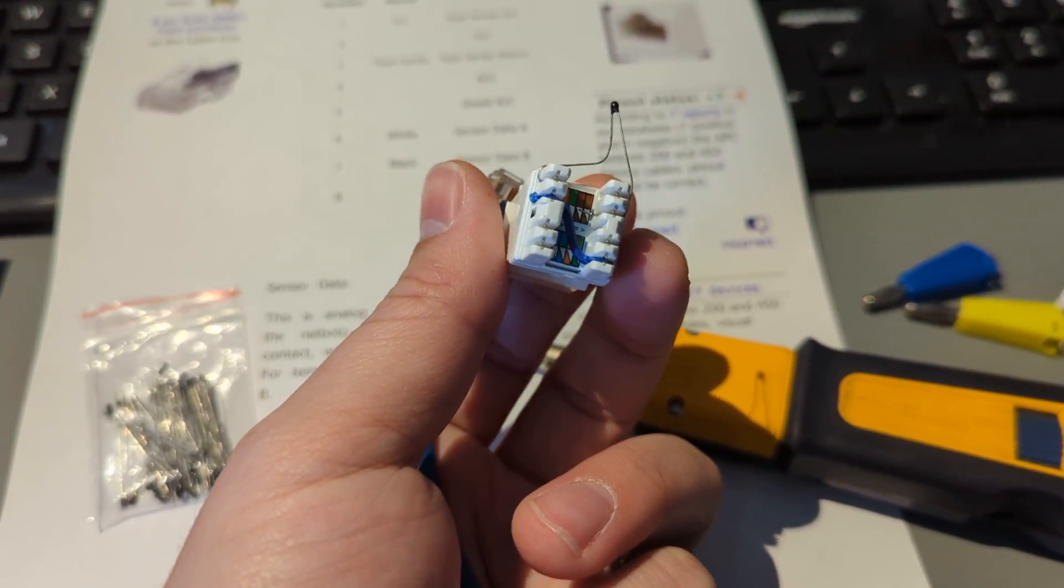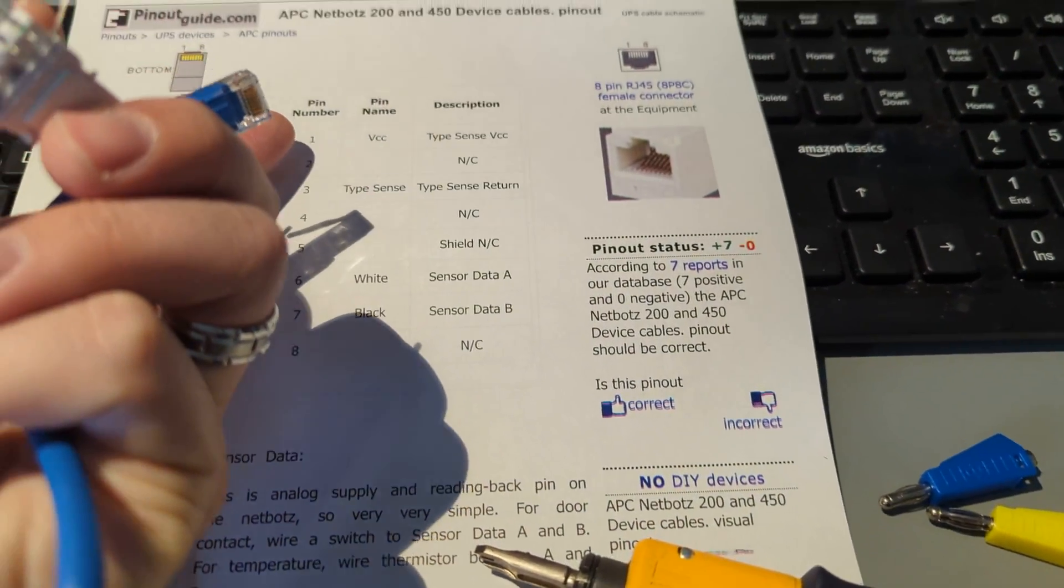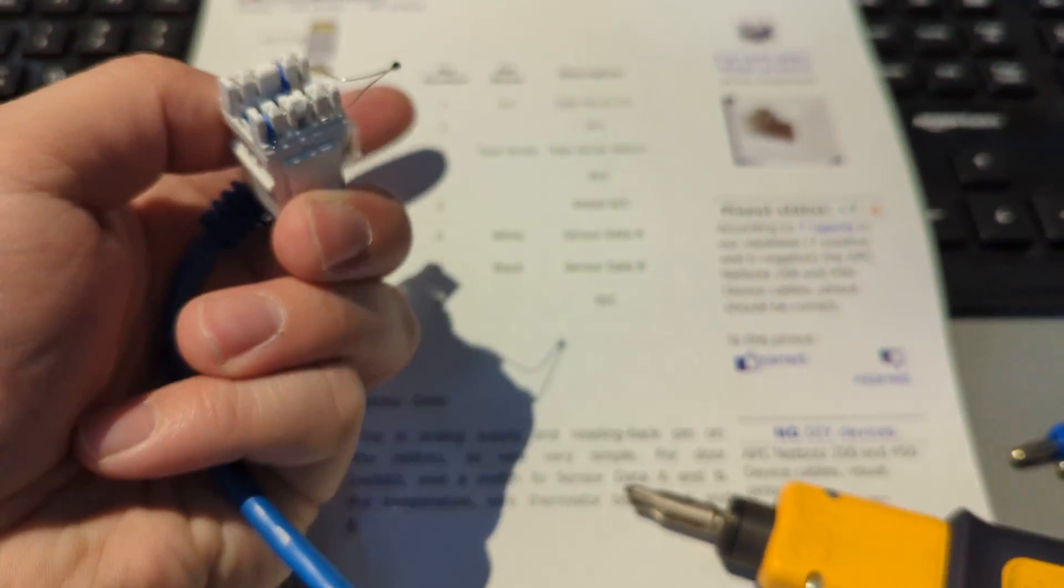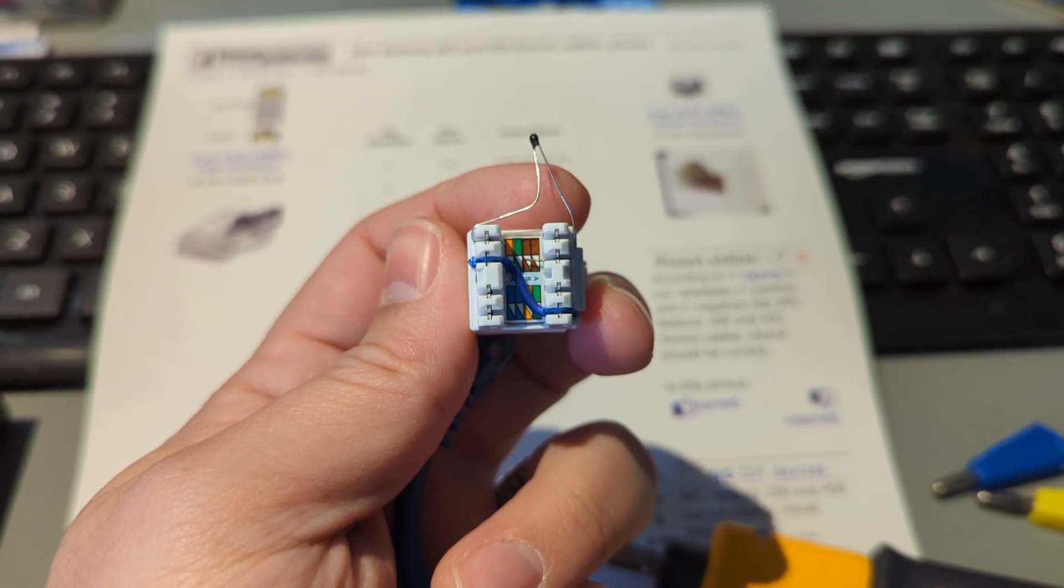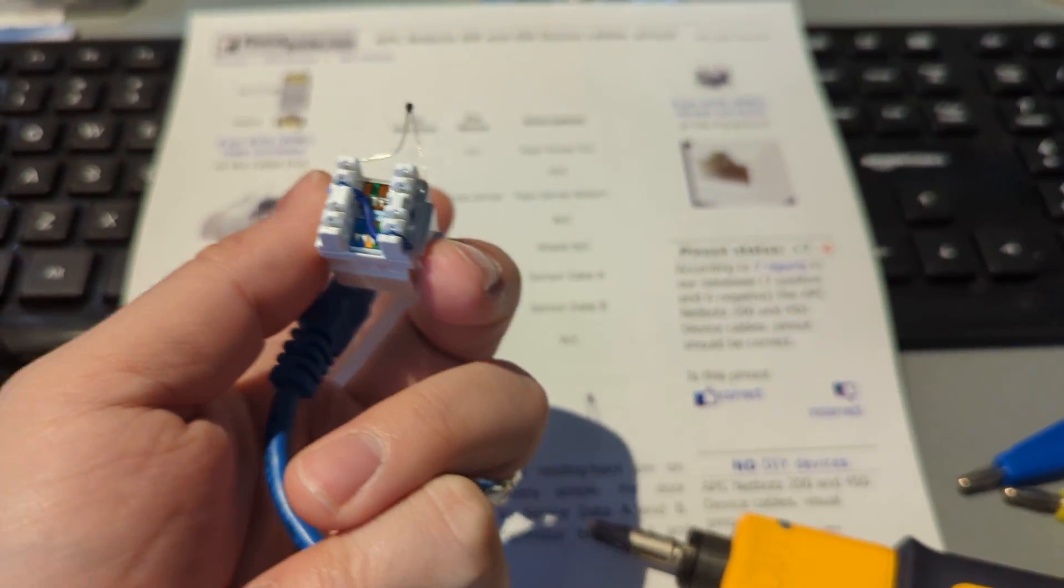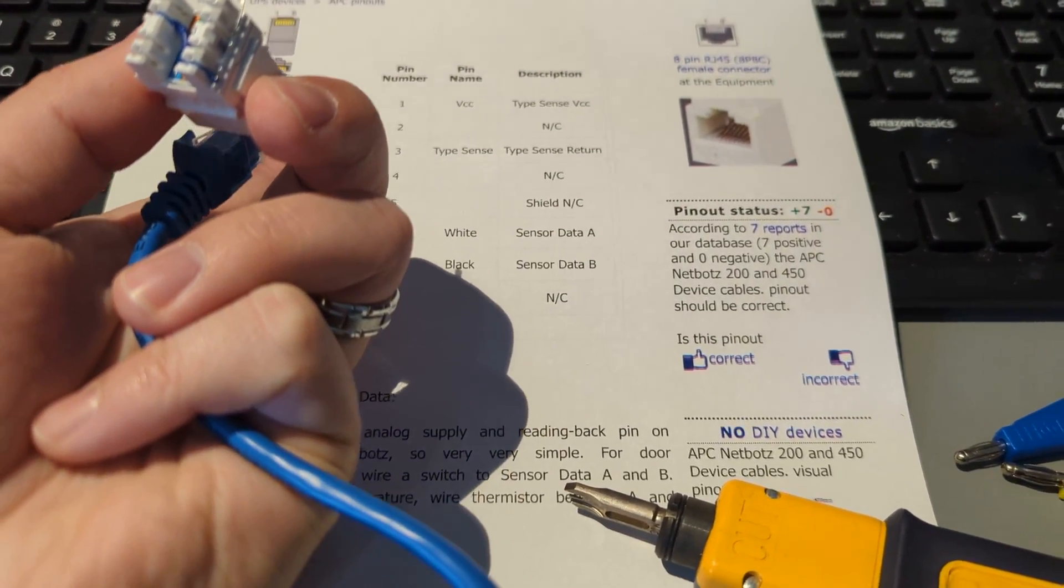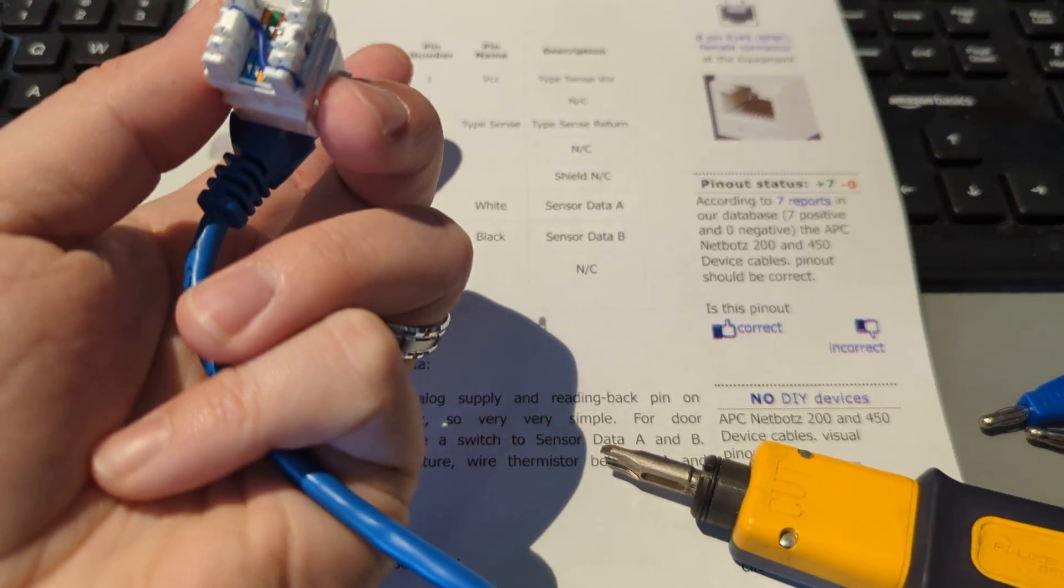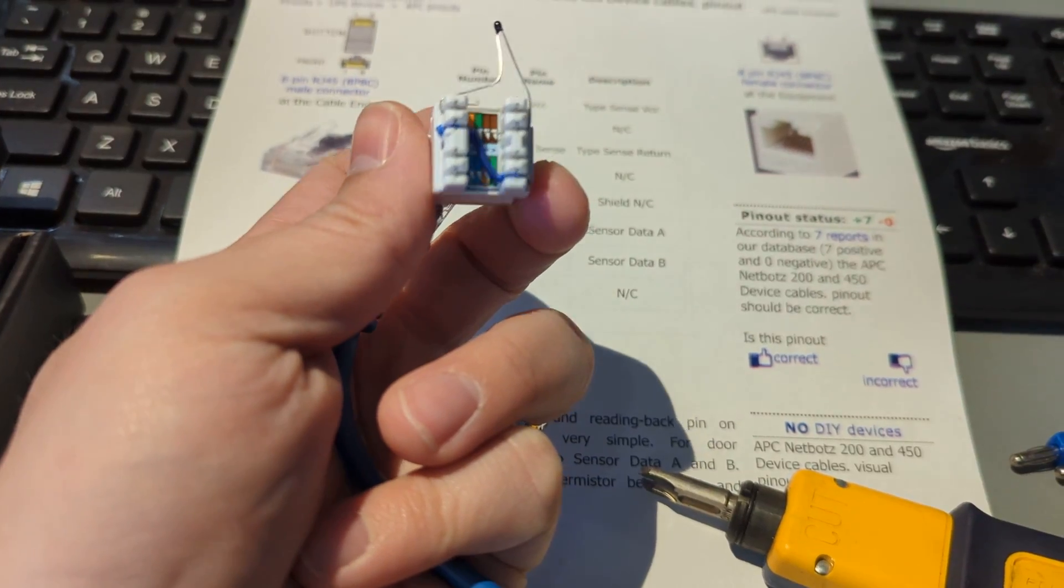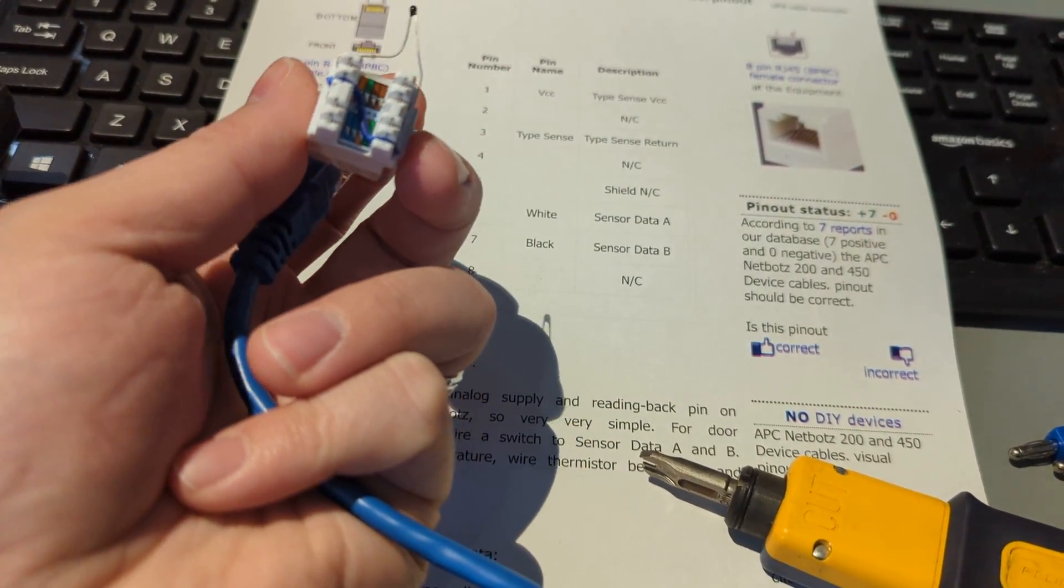All right, again, so using the pinout guide, the sense wires, right? So orange stripe, orange, green stripe. So between orange and green stripe, we're going to do a jumper, which is what we've done there. So that's the blue wire. And that jumper is a quote unquote zero to 4 ohm, right? Because that's the idea is with the cable length plus the jumper is between zero and four ohm for it to be a temperature sensor.